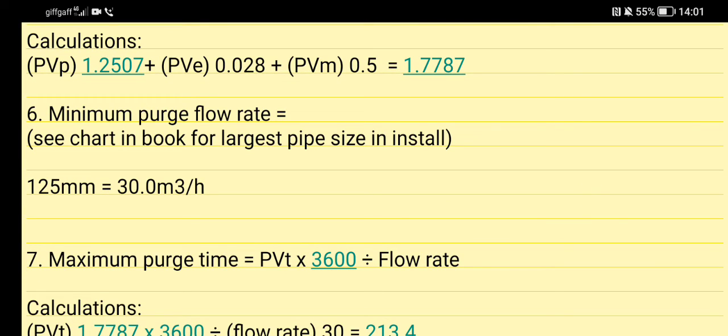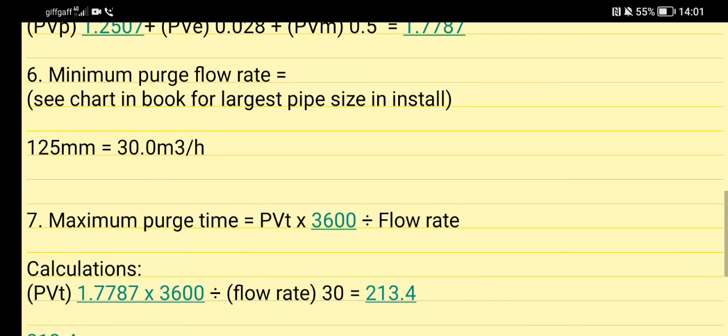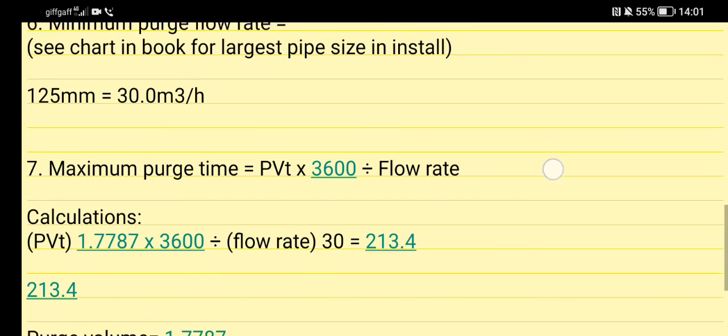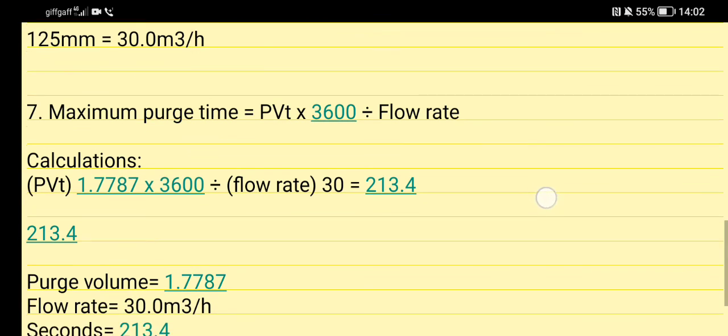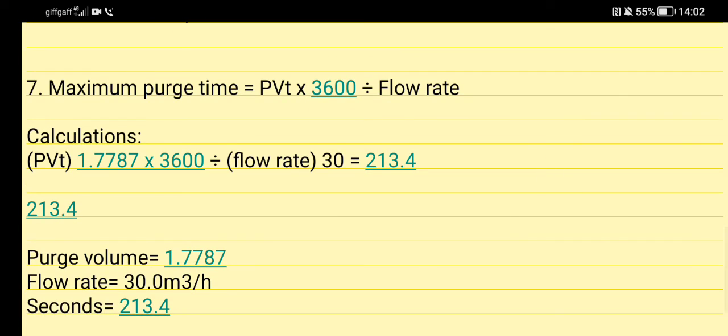Minimum purge flow rate now - you have to see the chart in the book. I showed you a picture earlier of where I got that from, and that shows me my purge flow rate. Then I get my maximum purge time. Now my PVT, I times that by 3600 and then I divide that by the 30 of my flow rate, and that gives me 213.4 seconds. I can divide that to get my minutes.